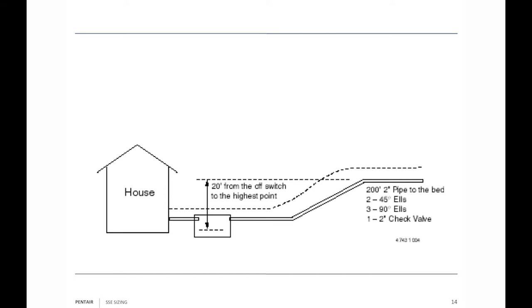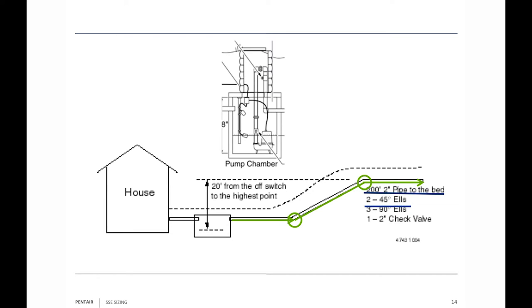Looking at the system layout, we've got 200 feet of two-inch pipe to the bed. That 200 feet includes two 45s and three 90s, plus the pipe inside the pit. There's also one check valve in the system. Remember, we talked about being able to pull the pump out without putting your face below ground level. Also, don't forget to drill the 1/8-inch hole one to two inches above the discharge pipe for priming purposes.